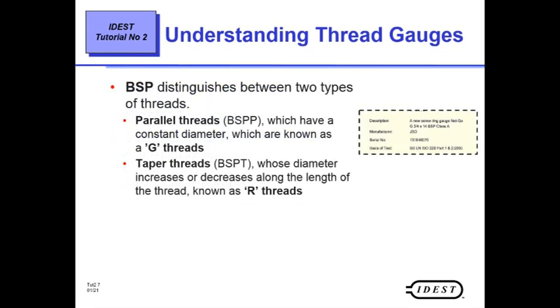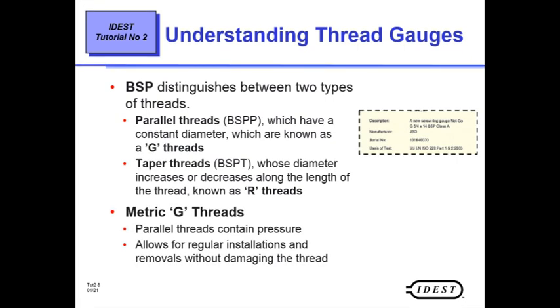Now we come to looking at the types of threads. BSP distinguishes itself with two types, a parallel thread and a taper thread. The parallel threads are signified by the letter G and the taper threads by the letter R. That's why on a calibration certificate you often see the letter G in front of the 3/4 or the G in front of the 5/8 thread. Metric threads also use G as a signifier, and this is also for parallel threads that contain pressure, and it means that these particular threads are able to be installed and removed from a device without causing any damage to the thread.